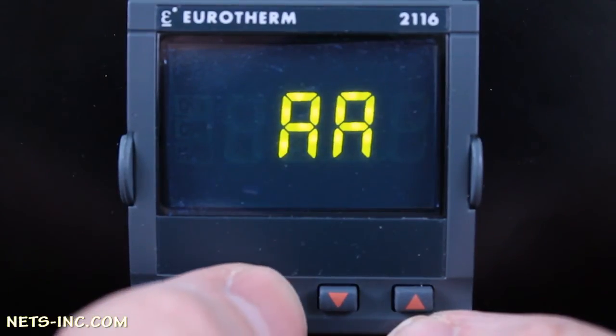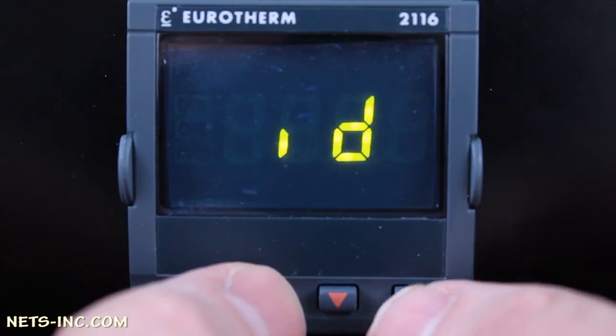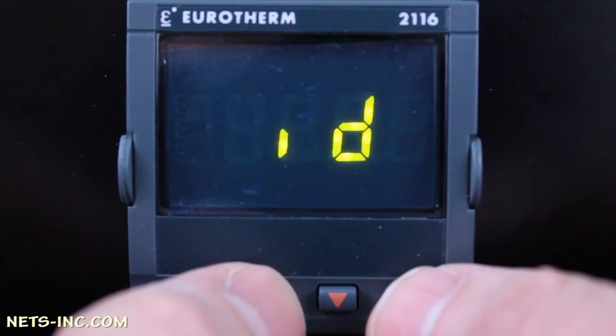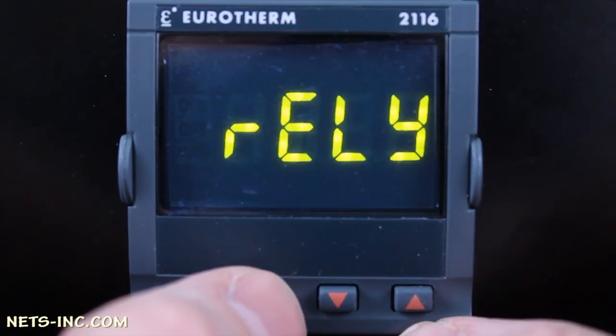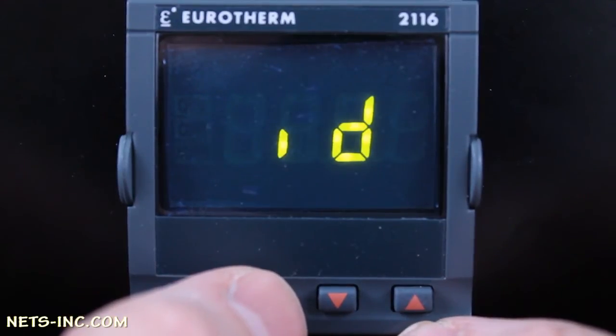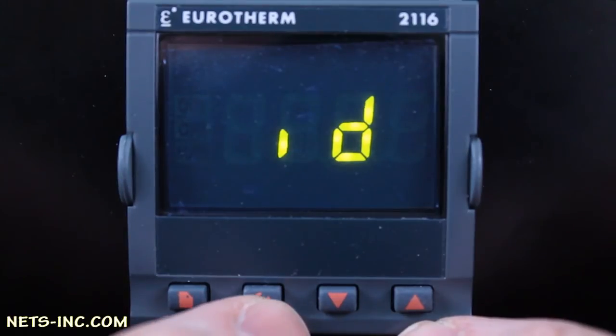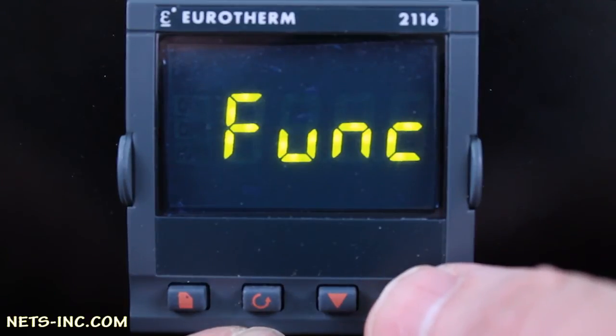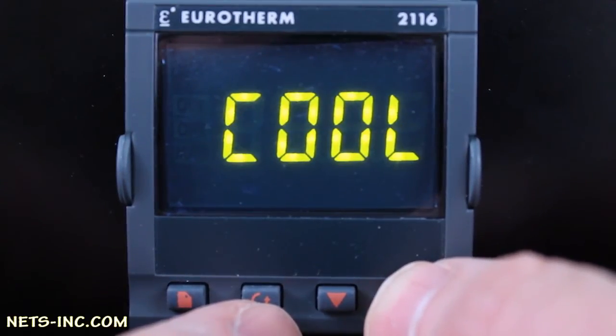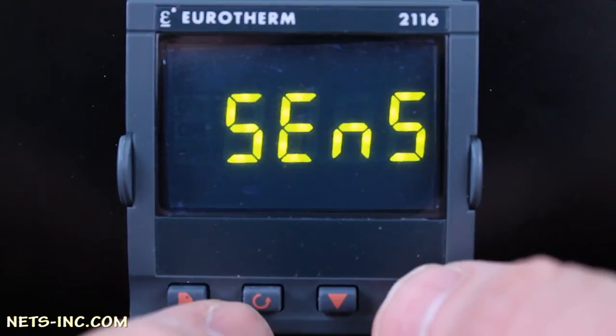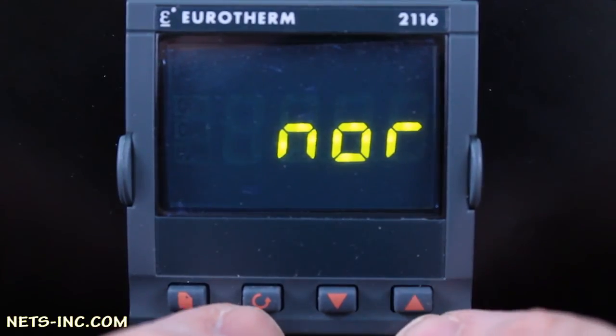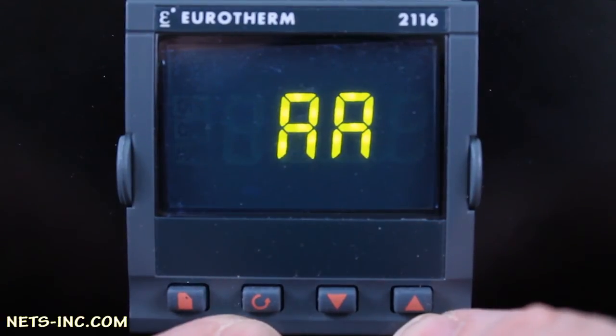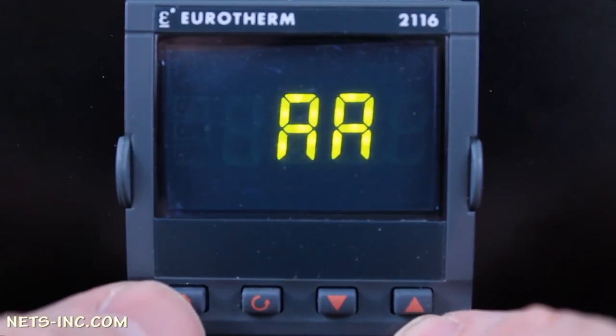Press the scroll key once to drill down into the AA list. The display will read ID. Press the up arrow to verify that ID equals RELY or relay. Press the scroll key once and the display will read FUNC. Press the up arrow key repeatedly to change the FUNC to COOL. Press the scroll key and the display will read SENS or SENSE. Press the up arrow to ensure that the display reads NOR for normal. Press the scroll key once and you are back to the display reading AA.